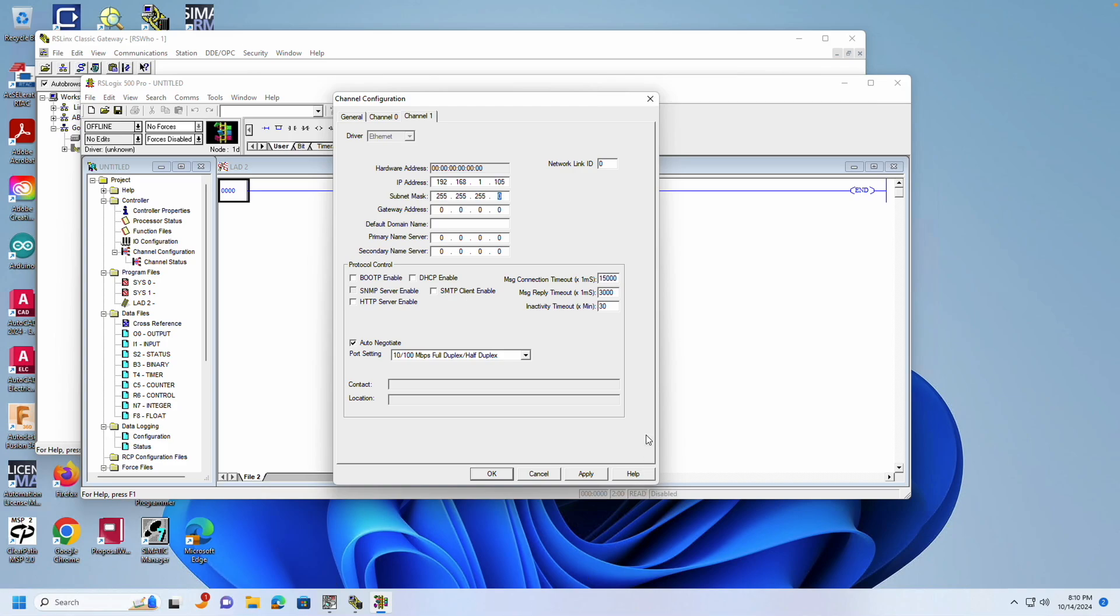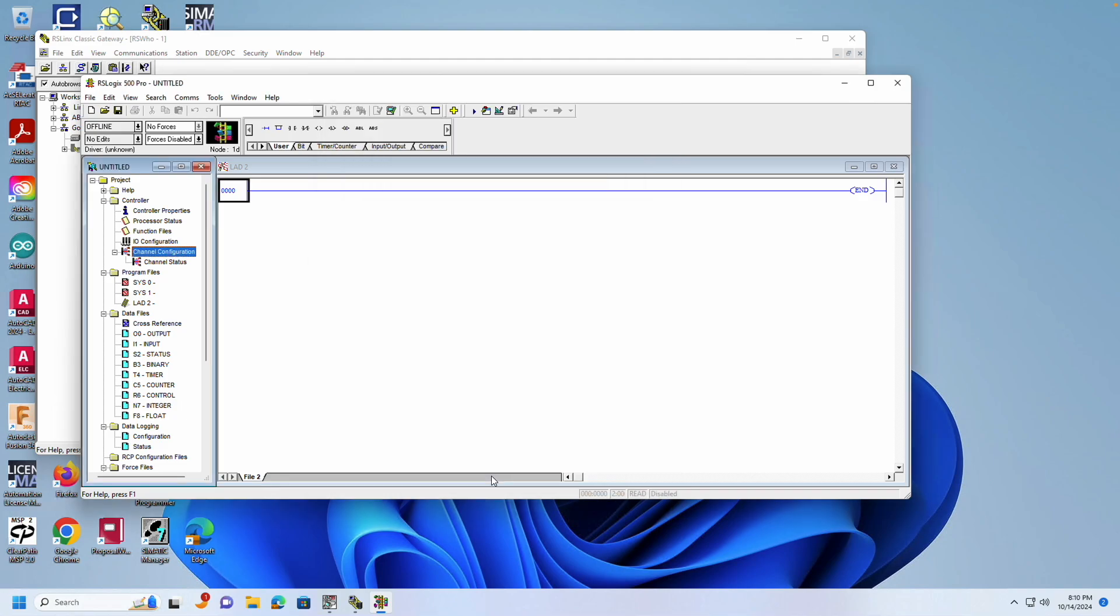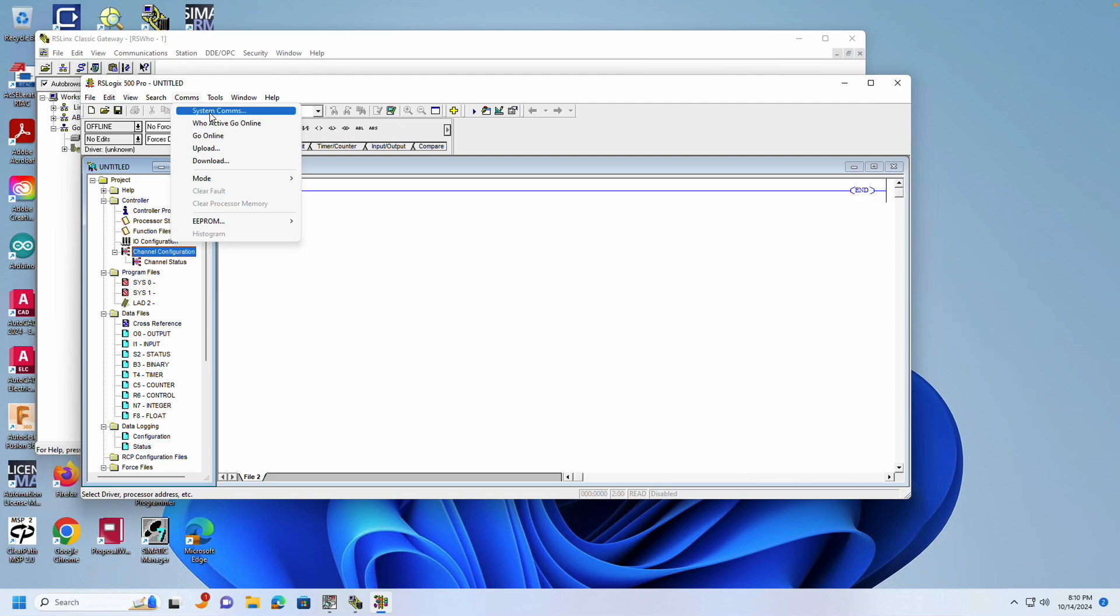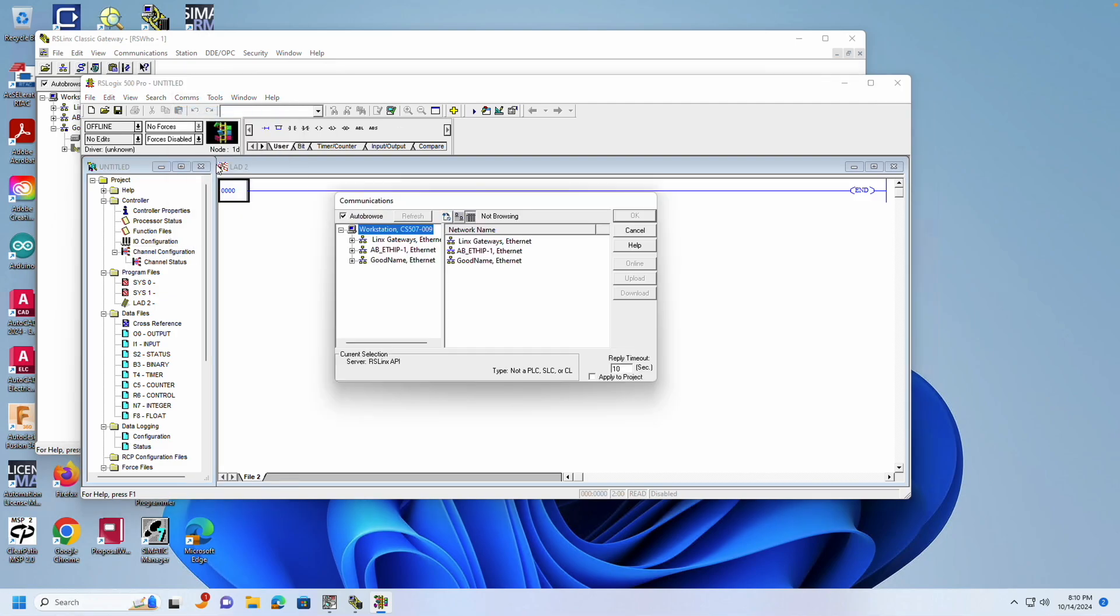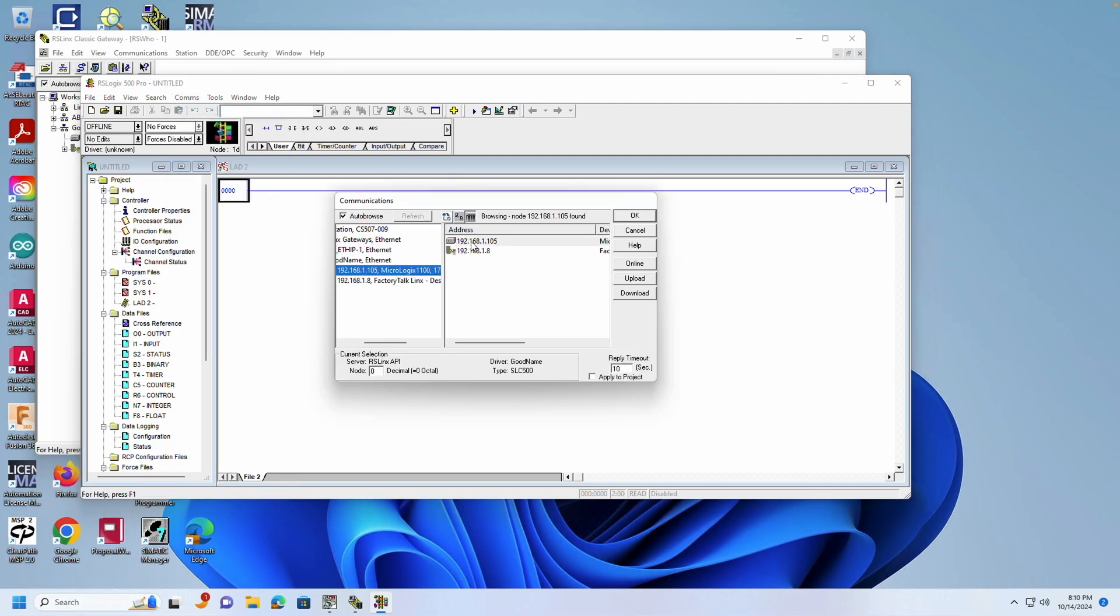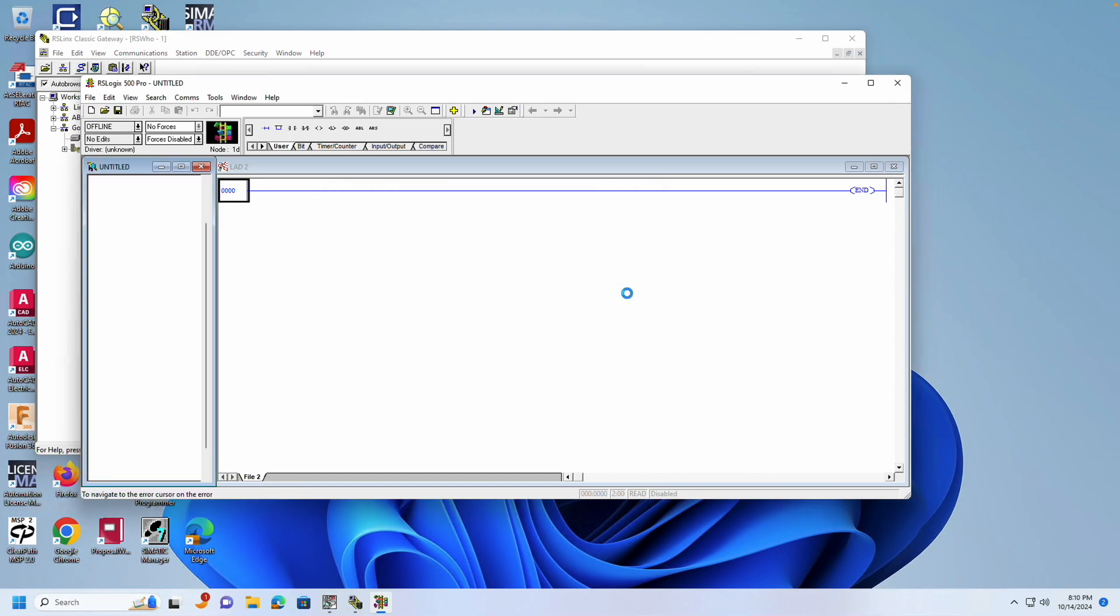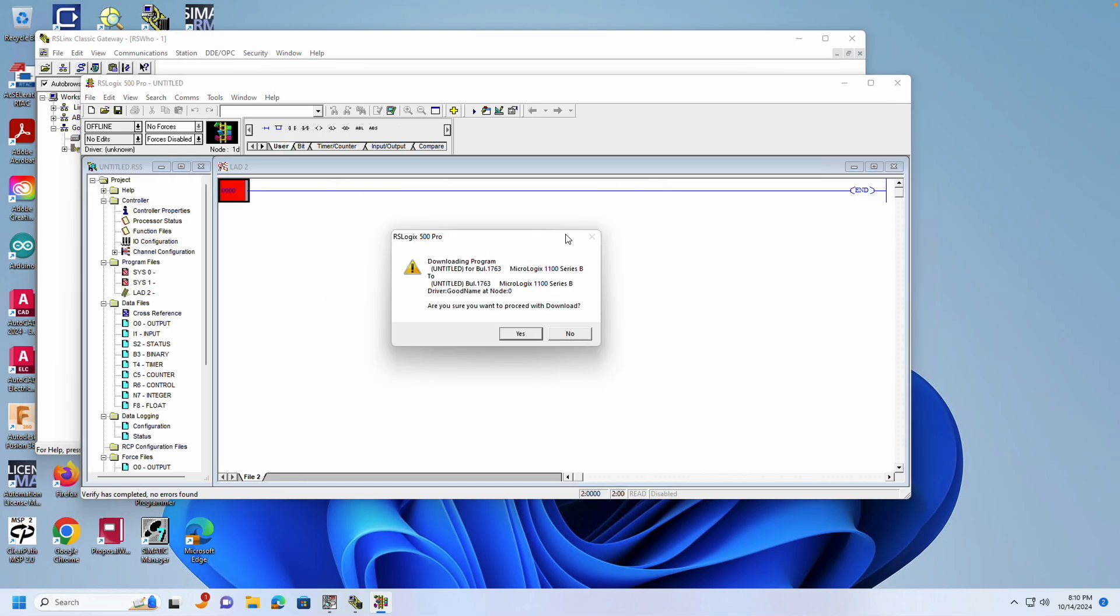To finalize the process, the program will need to be downloaded to the controller. Since we've changed our driver settings, go to Comms System Comms. Find your new driver and click on it. Your PLC should appear in the right pane. Select the PLC and choose Download. You will be prompted with a series of questions, answer all of them in the affirmative.